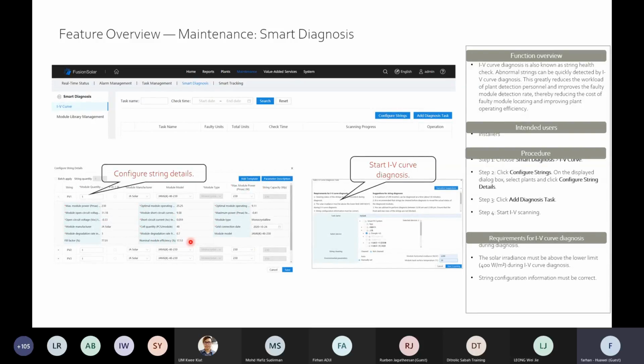After you do the configuration, make sure that your actual design matches whatever the installer used on site. If this one is not matching, the system will detect it. Let's say for PV1, in your design you set this PV module, but on site the installer did the termination on PV number 2. The system will detect an error, open circuit, or show wrong configuration. So it's useless unless you make sure this is correct first before doing the configuration string.